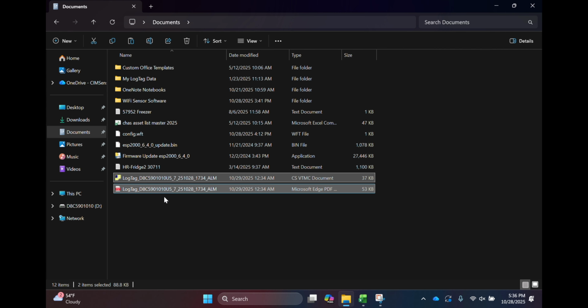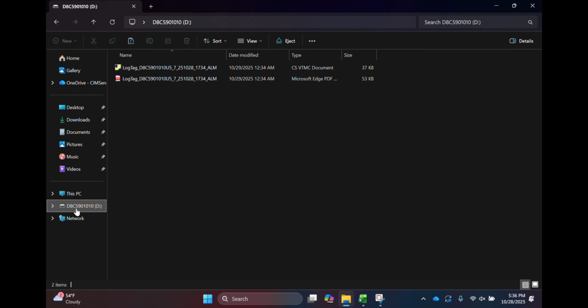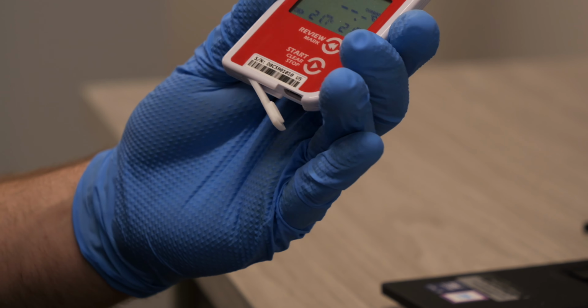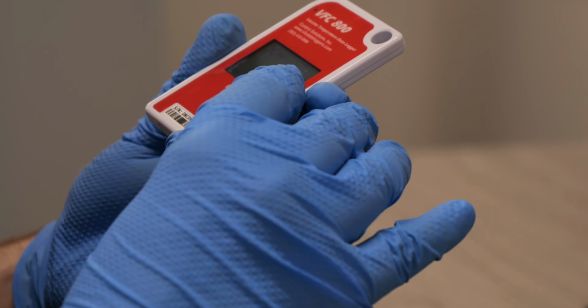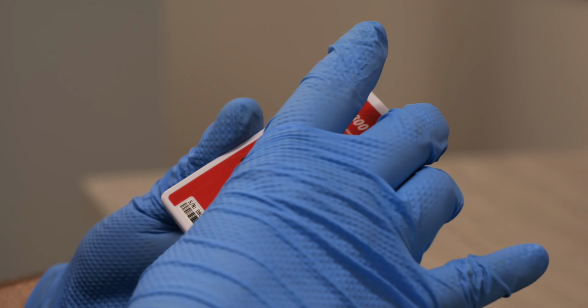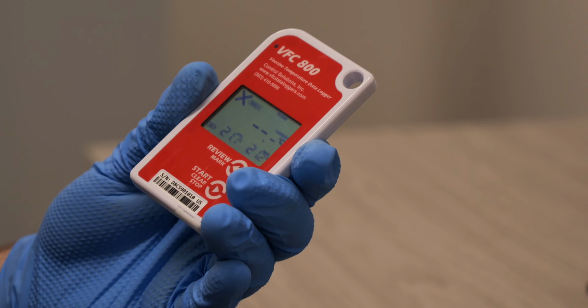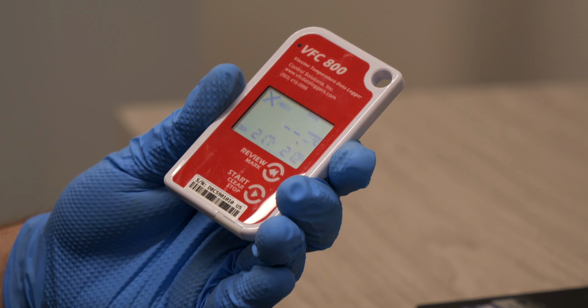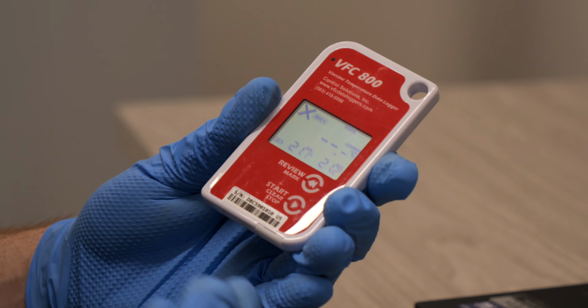Now I can go back to my data logger within my file browser, and what I'll do is just simply disconnect my data logger from the USB-C cable. I'm going to take it back, plug it into the probe at the fridge site, and the logger will continue recording. We do not need to stop logging to do the download.